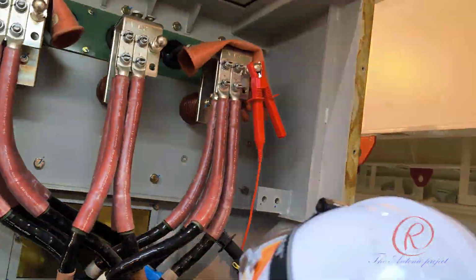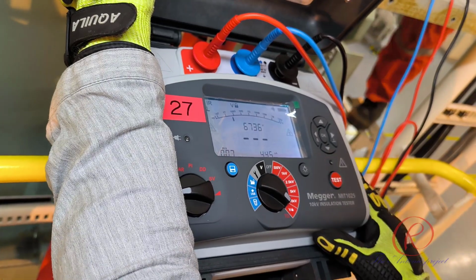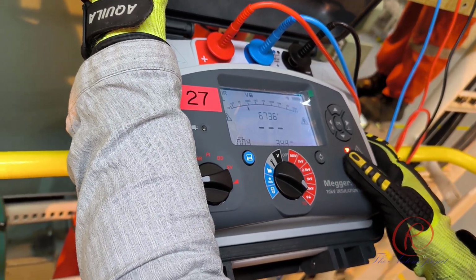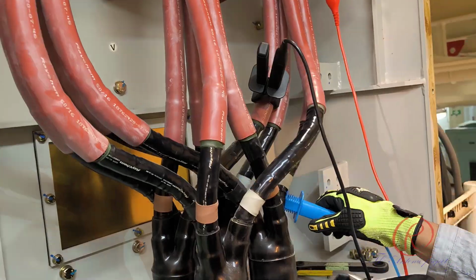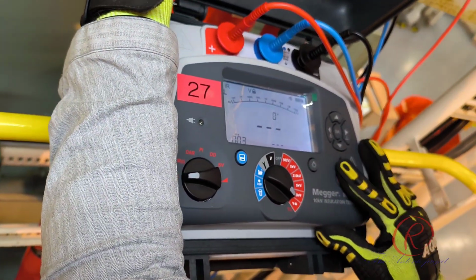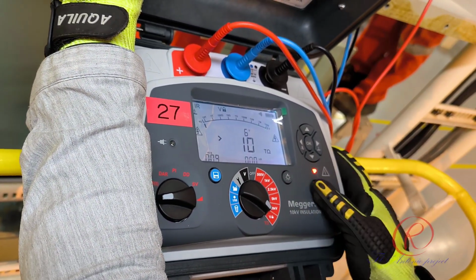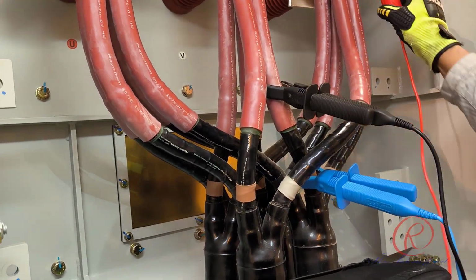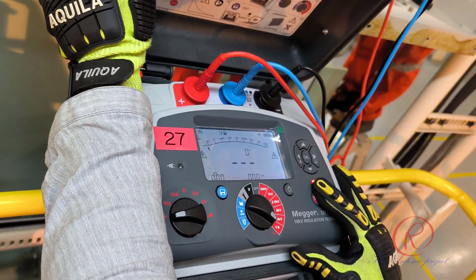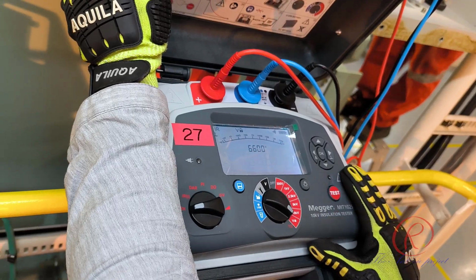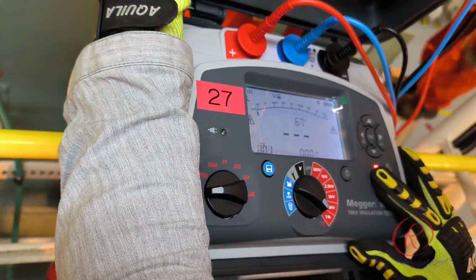Perform high voltage insulation resistance testing on a systematic and regular basis because insulating material tends to break down over time and with use. From the result of measurement, confirm that all cables are in good condition.